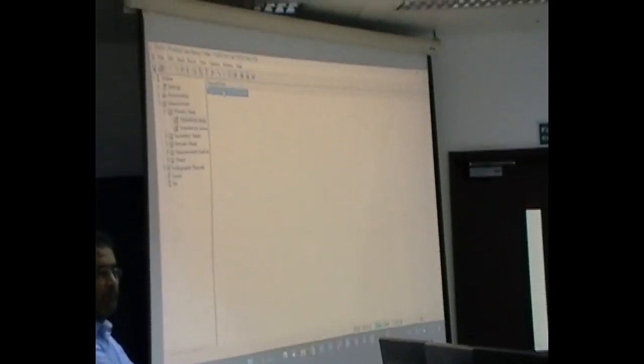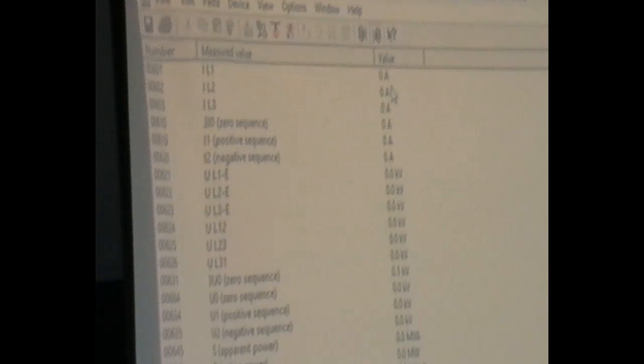So I will start the measurement, and you will record whatever we are injecting and whatever you expect in the primary, thus you will see it in the relay, and where it's coming, either red, yellow, blue, or neutral. You will record from here. Currently, I'm not injecting anything. I hope it's clear. I'm not injecting anything, so it's 0 ampere and 0 voltage. And we have also the positive, negative, and 0 sequence. We'll start injecting. I already started injecting 110 voltage to operate the relay. So the relay is on now. After the auxiliary supply from the Omicron, I'll go through the test.